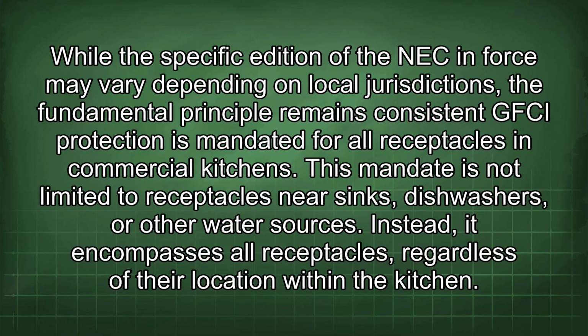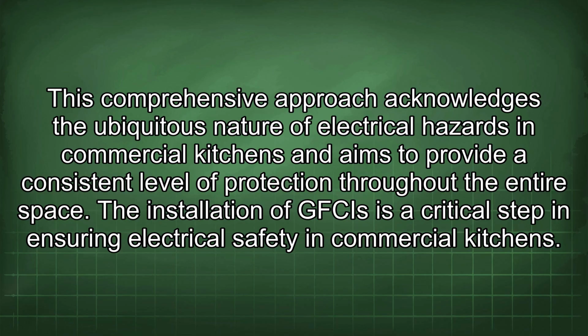GFCI protection is mandated for all receptacles in commercial kitchens. This mandate is not limited to receptacles near sinks, dishwashers, or other water sources. Instead, it encompasses all receptacles, regardless of their location within the kitchen. This comprehensive approach acknowledges the ubiquitous nature of electrical hazards in commercial kitchens and aims to provide a consistent level of protection throughout the entire space.